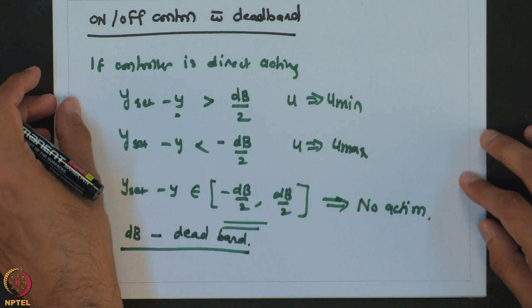So, the effect of dead band is, as the dead band increases, y set minus y increases. That means, I will say, the average value of that, so that means larger deviation from the set value, but this comes at an advantage that our valve toggling reduces. So, the higher dead band is used to avoid the valve going from on to off position at a much higher frequency. Typically the dead band is selected based on the trade off between how much deviation is allowable and correspondingly how much valve toggling is allowed. So, as a trade off between these two, the deadband gets selected.